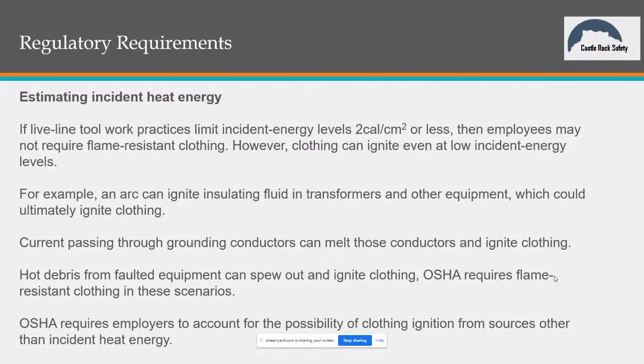But I'm on the end of an 8-foot hot stick. Then OSHA says in that case, I do not have to have arc flash clothing on. Now, again, I'm not saying you wouldn't put it on, but if you look at the baseline requirement, you are only required to put that on if you're going to be inside that 2-calorie boundary. Well, from the sounds of it, even the office people have 2-calorie on. They do. That's the point I'll make later, is that a lot of this is moot because they're just putting it on everybody.